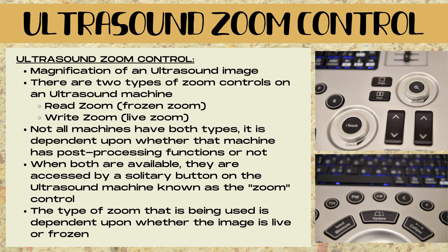Not all ultrasound machines have both types — it's dependent upon whether that machine has post-processing functions or not. When both types of zoom are available, they are accessed by a solitary button or knob on the ultrasound machine known as the zoom control, and the type of zoom being used is dependent upon whether the image is live or frozen.